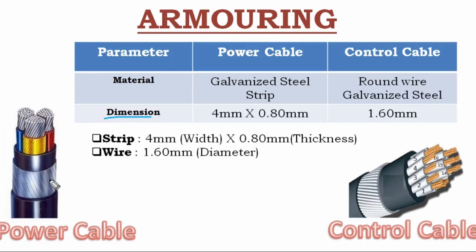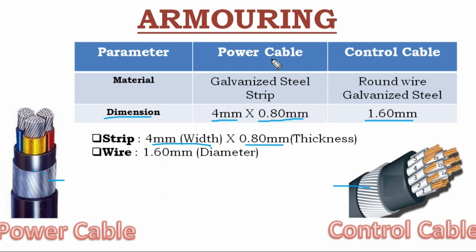The armor dimensions are: for the power cable, 4 mm width by 0.8 mm thickness — it is a flattened strip, so width and thickness are specified. For the control cable, the round wire diameter is 1.60 mm. Hence the power cable armor is specified as 4 mm × 0.8 mm, and the control cable armor wire diameter is 1.60 mm.